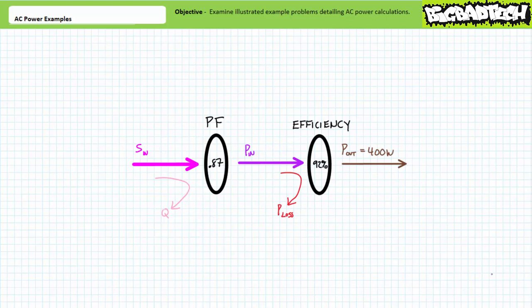Let's come at this from yet another direction. Consider a motor nameplate that explicitly states a motor produces 400 watts of real mechanical power output and has a 0.87 power factor and is 92% efficient. This means for the motor to yield the desired 400 watts of output mechanical power, it necessitates at least 400 over 0.92, or 434.8 watts of real electrical input, of which 34.8 watts is lost due to inefficiencies. This additionally means that this motor must consume 434.8 over 0.87, or roughly 499.8 volt amperes of apparent power. The 246.4 VARs of reactive power, while essential to this motor's operation, is excluded from consideration by power factor.